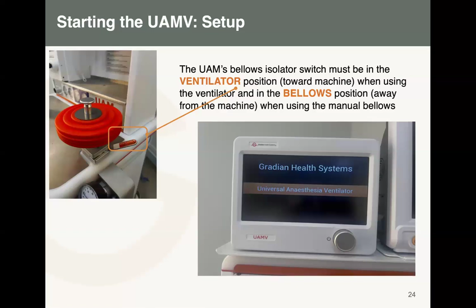So this is what I said. When switching on, after the previous screen, this is what will come. You have two options. Go with the user ones, which are pre-saved by the user, or go for the default ones, which have been set in the machine. As you can see, we have 10, 25, 50, 70, and 100 kg. On this one, you can see we selected the 70 kg one, and these are roughly the parameters which the machine will use to ventilate the patient. As I said before, these are estimates, so they depend on your patient. Once you select this, you can go in and review and make sure they are appropriate for the patient you're operating. Next.